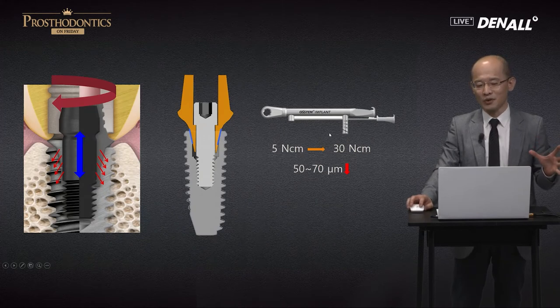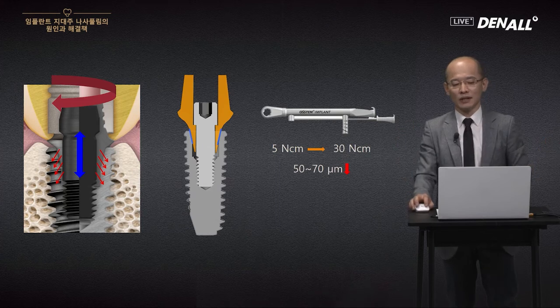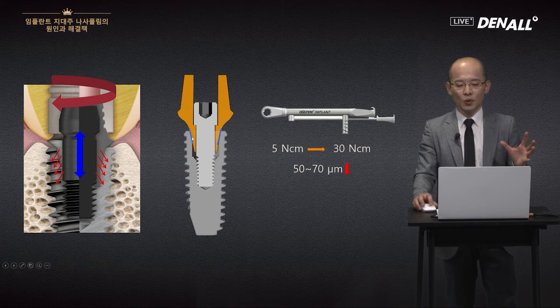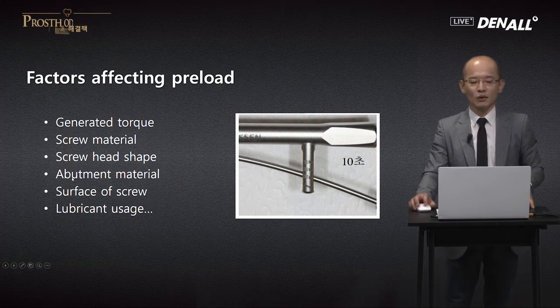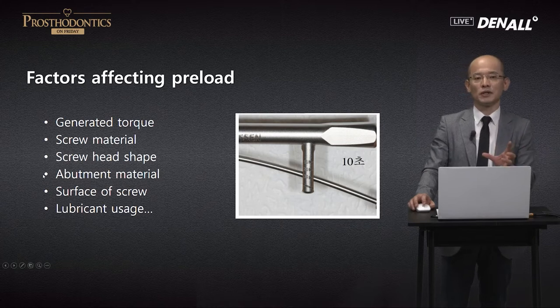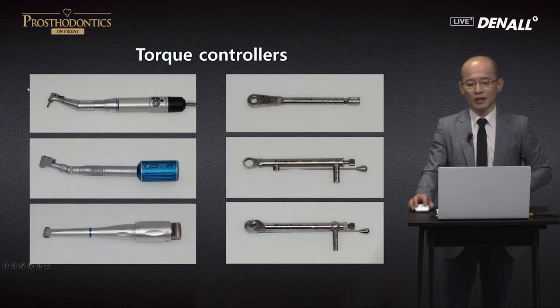We use a torque controller for preload, and it's well defined now. You have narrow, regular, and wide platforms, and you choose the right one. Typically about 30 newton-centimeters is available. For the internal implant, the conical seal reduces the overall axial displacement by 50 to 70 micrometers. These are the factors affecting preload. To control this, implant makers use coatings, change materials, alter abutment dimensions, or standardize torque drivers.